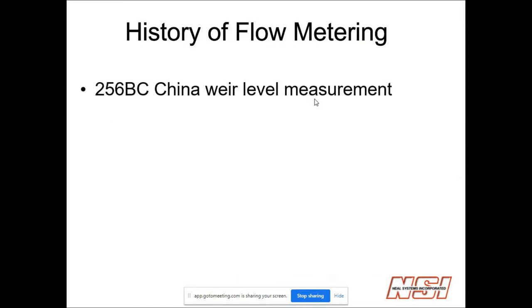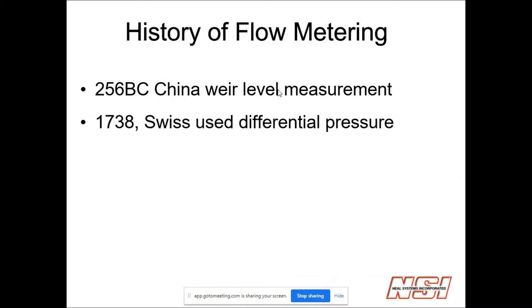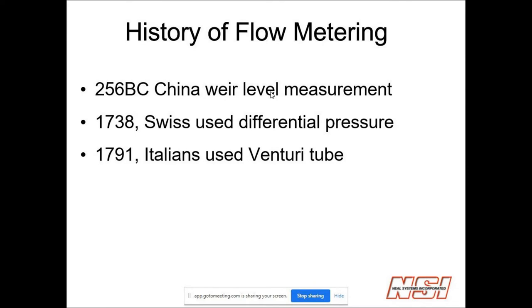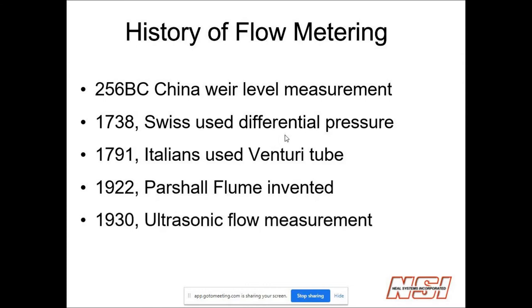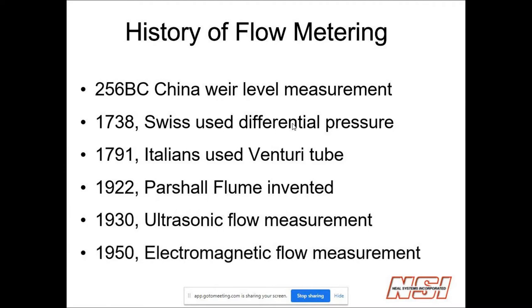A little history of flow metering. In China, 256 BC, somebody looked at a dam they built and said the level's going up as the flow increases — they were measuring flow by how high the level was over the top of the dam. In 1738, the Swiss used a differential type of flow measurement. In 1791, the Italians used a Venturi tube. In 1922, the Parshall flume was invented by Bob Parshall. In 1930, ultrasonic flow measurement. And 1950, electromagnetic flow measurement. Today we're focusing mostly on what you might see in a wastewater or water treatment facility.